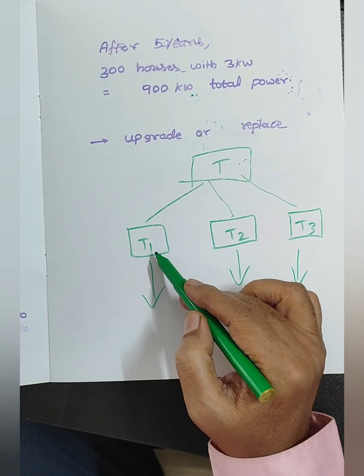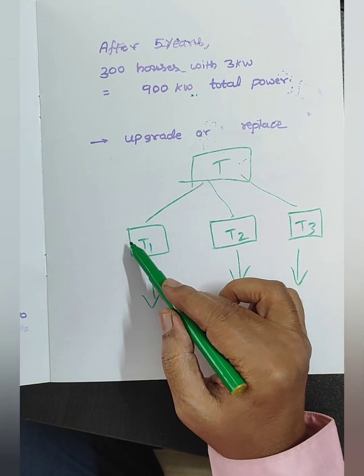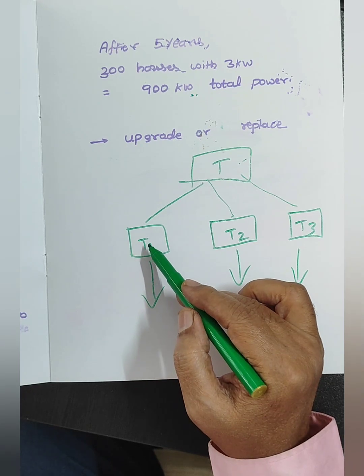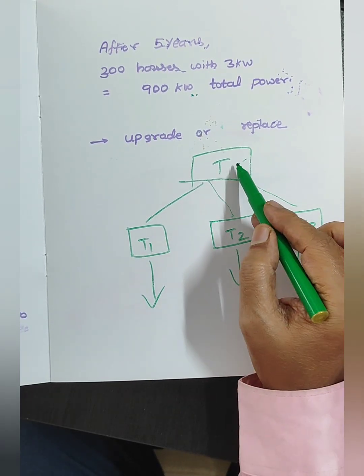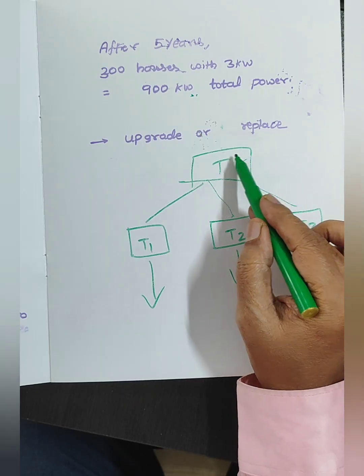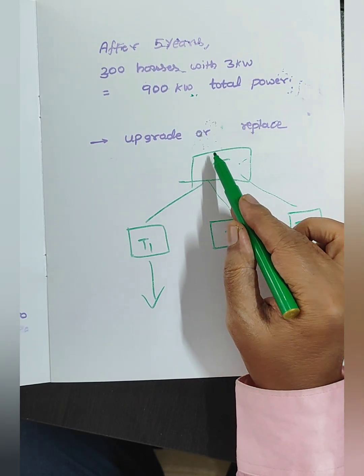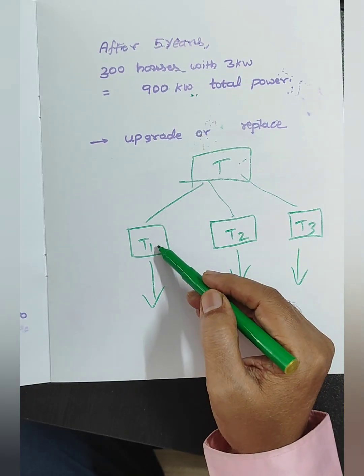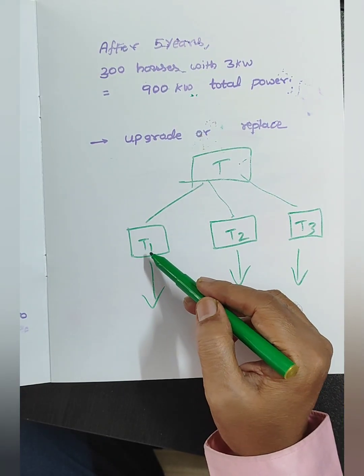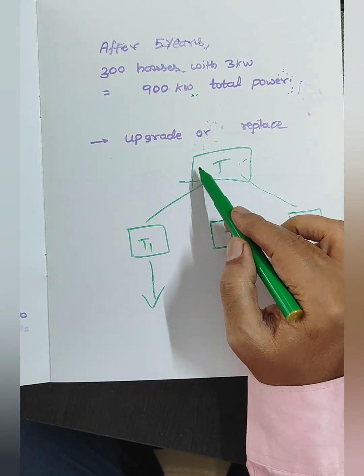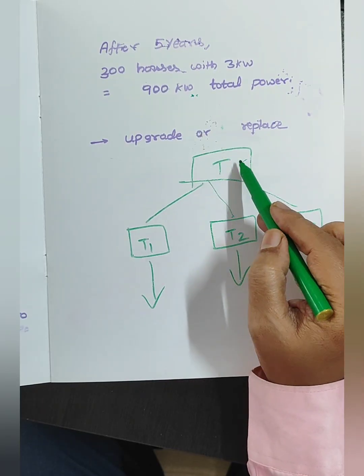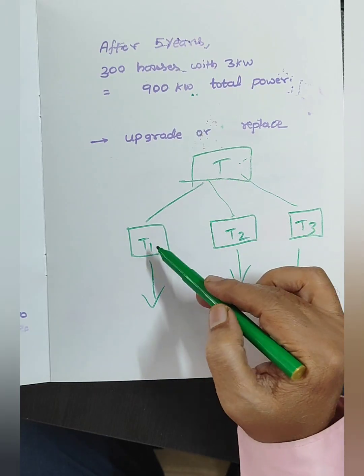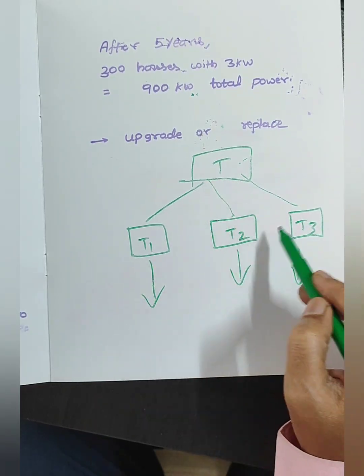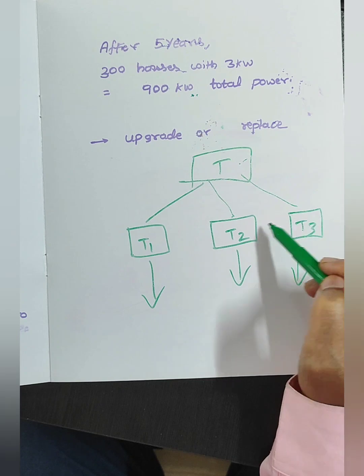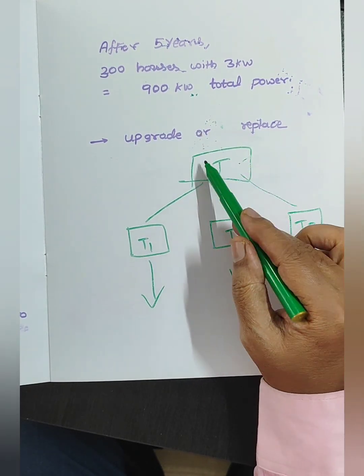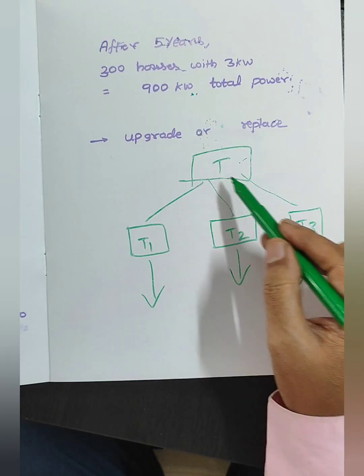In effect, upgrading or replacing one transformer itself is a huge task, and while doing so we incur another bigger problem, wherein a big transformer also has to be upgraded or replaced. Remember, if a small transformer burns out, it takes about 2-3 hours to repair, but if the bigger one burns out, it takes 2-3 days or even more. Therefore, they have balanced all these powers, and depending upon these capacities, they have installed a bigger transformer. This is called the cascading effect.